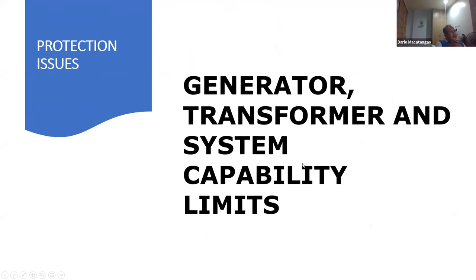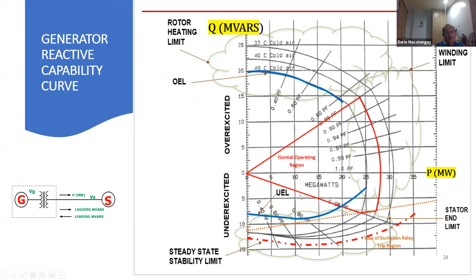Okay, we go to the generator transformer system capability limits. Are you familiar with the reactive capability curve? This is something to do with, again, from our simple generator, we need the magnetic field, right? And we need that to either boost the voltage or reduce the voltage. So the voltage and the excitation have something to do with the flow of the MVARs. It's inductive reactive power.